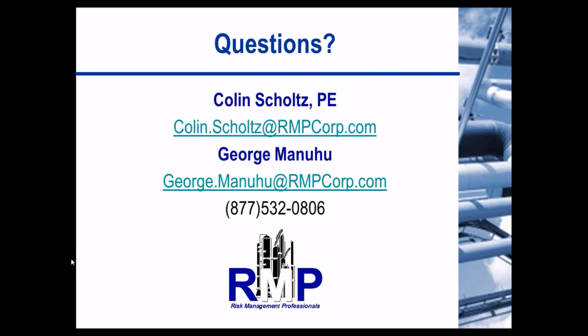And then also, most of you probably are aware of this, but when we do talk about corrosion, we're talking about typically external corrosion due to water or moisture, or internal corrosion due to any water that gets into the system. And just a quick note, I think most people have gotten this, but ammonia will react with copper, brass, or similar metals in your system. So if you haven't already, do a quick check on that. Typical materials that will react with ammonia include brass, copper and zinc. So let's open up to questions.